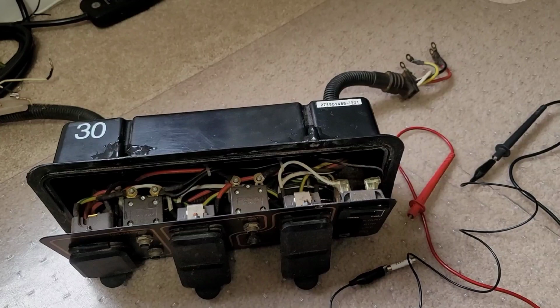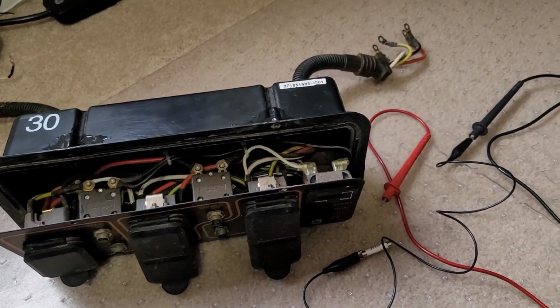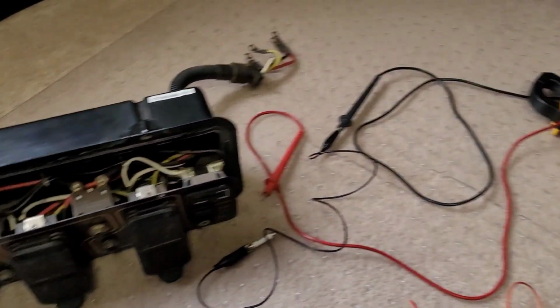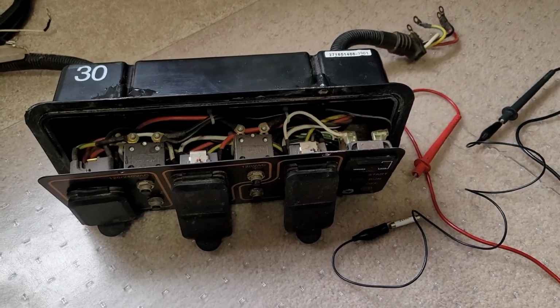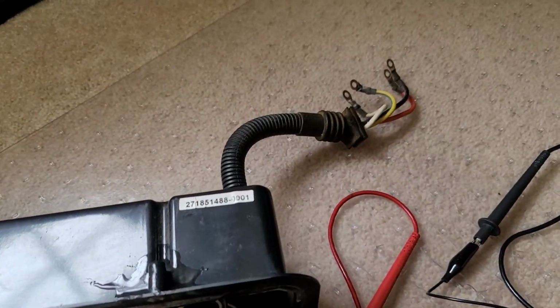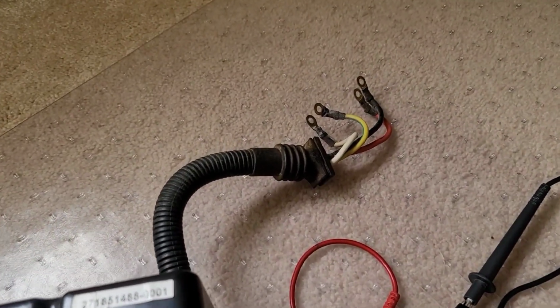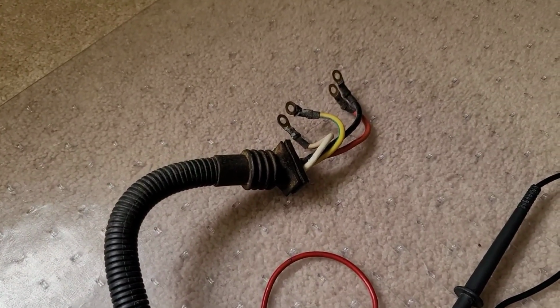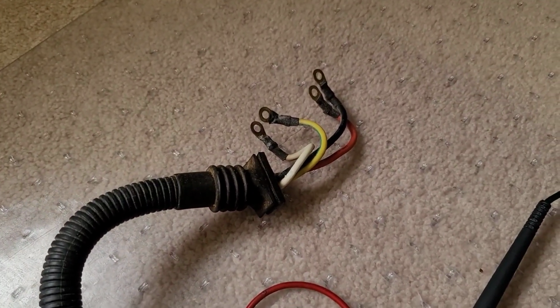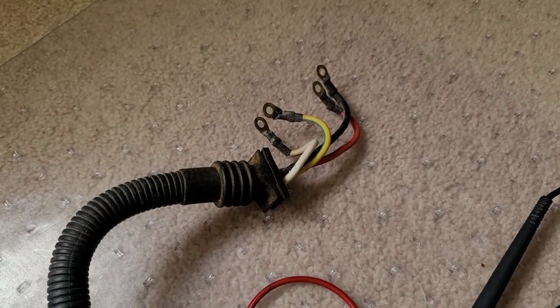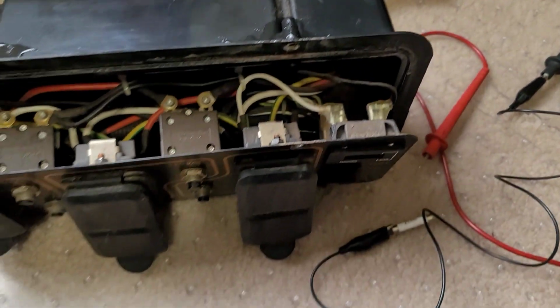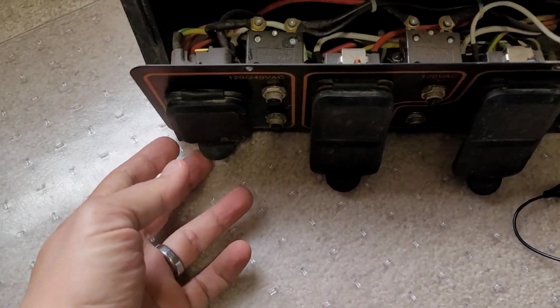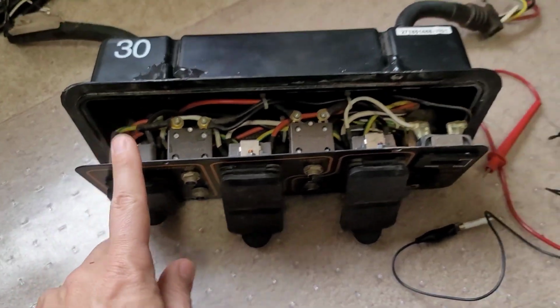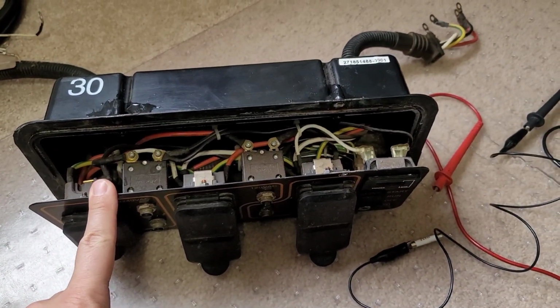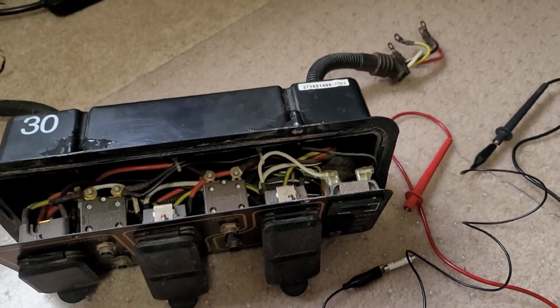I'm just doing some Murphy's Law preventative maintenance here, checking out the outlets to make sure that they're all functional, ohming out between the wires here that would go to the stator. You've got your two hots, the X and the Y on the red and blacks, and then your neutral white and your green, the earth ground that goes back up and runs to all the outlets here. Just making sure that we have continuity between the outlets and the wires going to the stator.